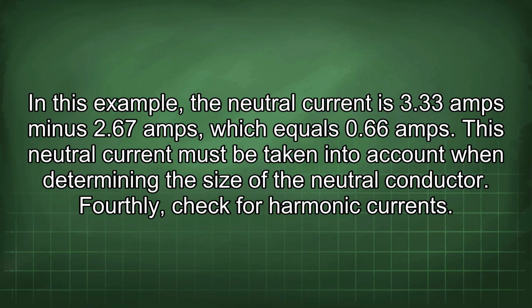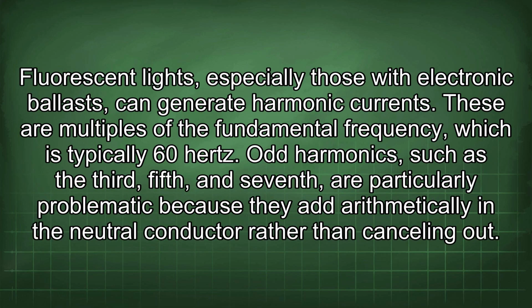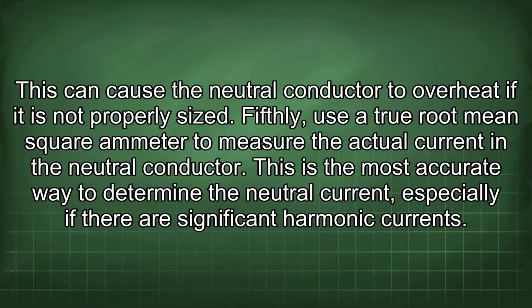Fourthly, check for harmonic currents. Fluorescent lights, especially those with electronic ballasts, can generate harmonic currents. These are multiples of the fundamental frequency, which is typically 60 Hz. Odd harmonics, such as the 3rd, 5th, and 7th, are particularly problematic because they add arithmetically in the neutral conductor rather than cancelling out. This can cause the neutral conductor to overheat if it is not properly sized.